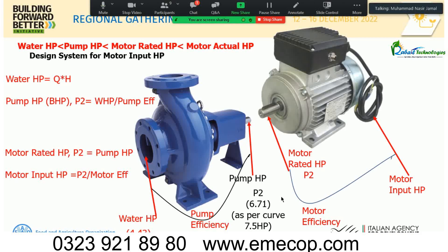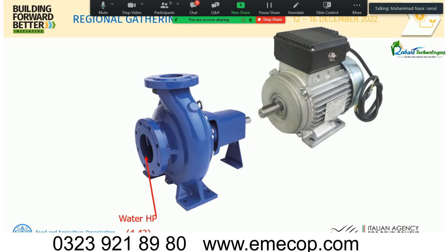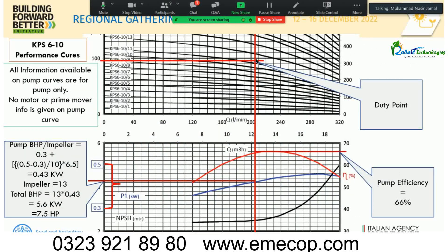Water horsepower is 4.4 HP and pump horsepower is 6.71 HP. Pump efficiency is 66% and we need a motor of at least 7.5 HP. However, we selected a 10 HP motor because we need to cover the entire pump curve. At the maximum power point on the curve, calculations show 8 HP is required. Since 8 HP motors are not available in the market, we must jump to 10 HP. As a rule of thumb: always size the motor to cover the entire pump curve, not just the duty point.